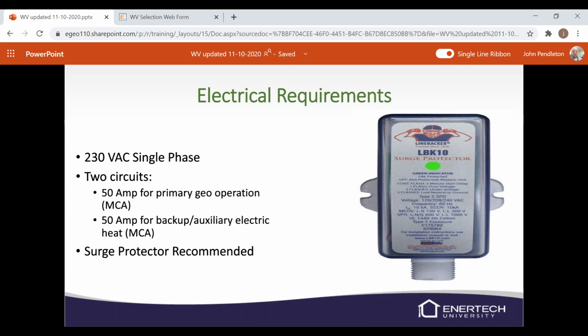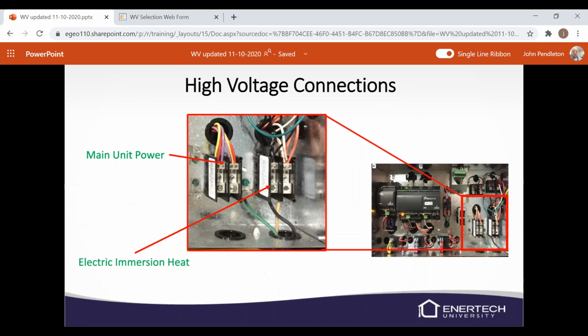We do recommend a surge protector and possibly even a compressor defender. I'll have to talk to Jim about that. Surge protector is nice, with all these electrical controls on here. A lightning strike or something can really take out and cause a lot of problems. So we like to put a surge protector on it. Again, there are 2 circuits, one for the geo and one for the backup or auxiliary heat, and it's 230 volt single phase only. Again, high voltage connections, they will be labeled, one for the immersion heater and one for the main power.